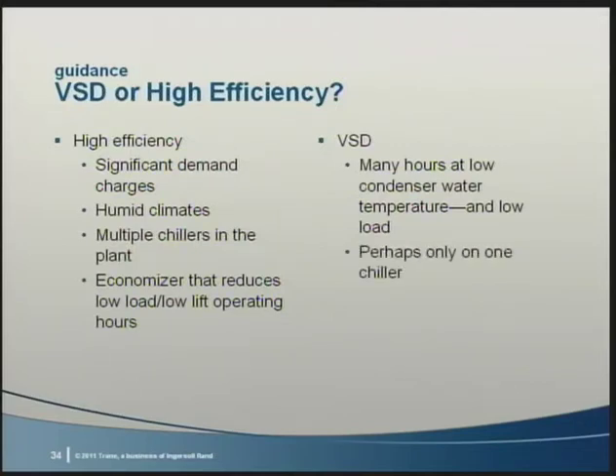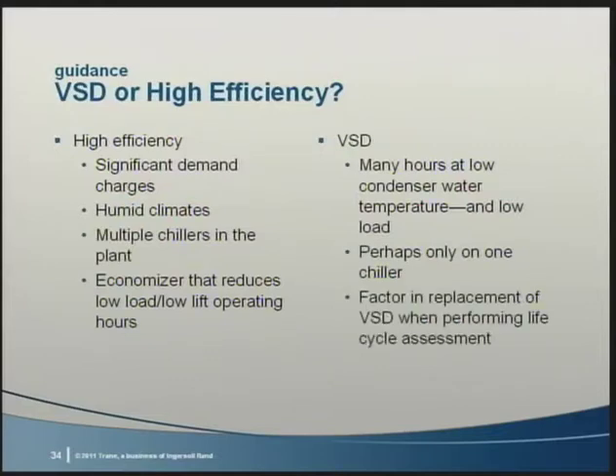Another issue that should be considered is the life cycle cost of the drive. A high-efficiency chiller uses more copper to increase heat exchanger effectiveness. In a properly maintained system, copper is very reliable and will last the life of the chiller. A variable speed drive will likely need significant investment, either a rebuild or replacement around once per decade. This cost must be accounted for in the life cycle assessment.